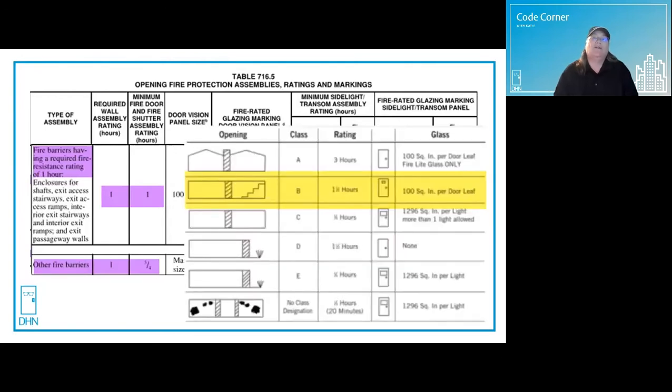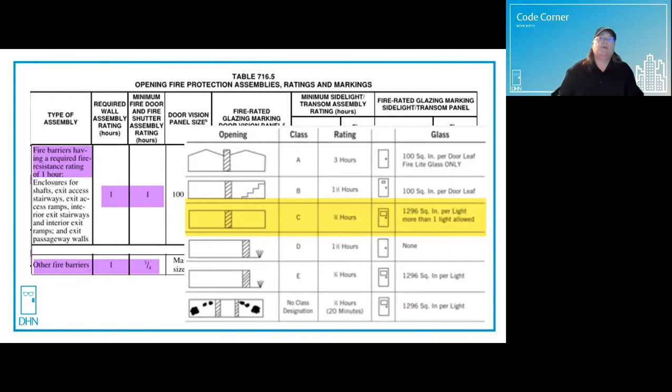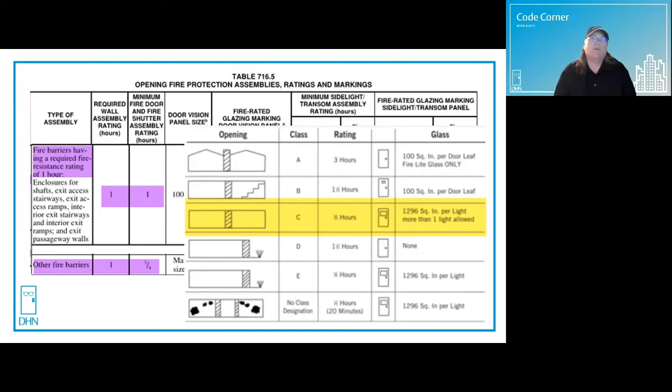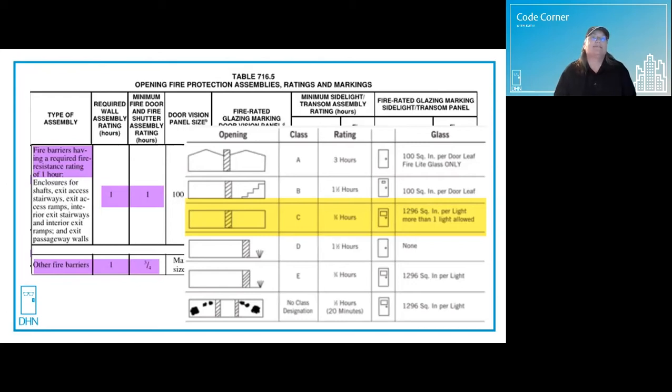Then there's this little almost gotcha called other fire barriers and a little further down the table, other fire partitions. This would include places like mechanical rooms, large storage rooms, laundry rooms, and other similar spaces. There'll be a one hour fire barrier or fire partition with a three quarter hour, also known as a 45 minute rated fire door. And that's classified as C-labeled.